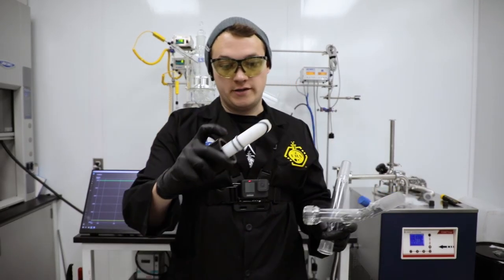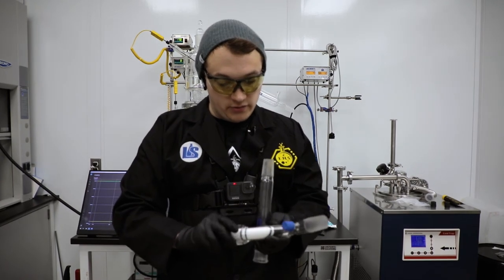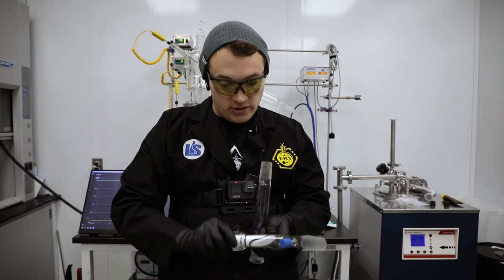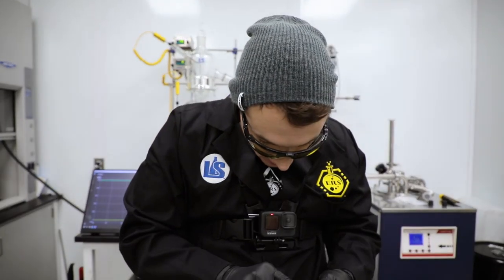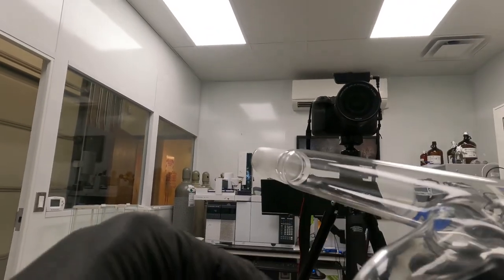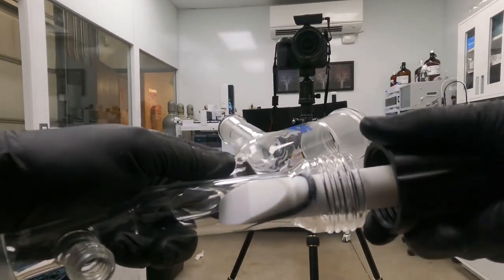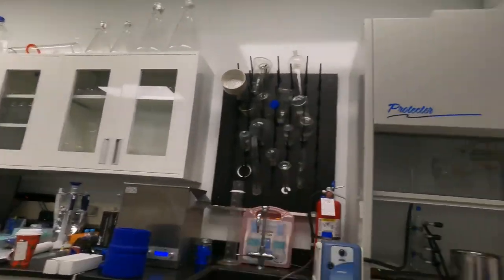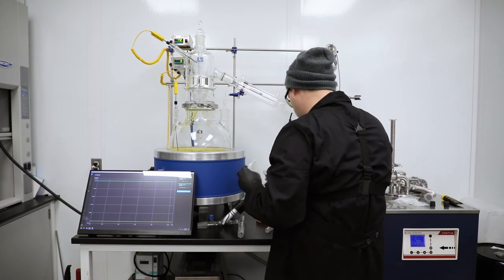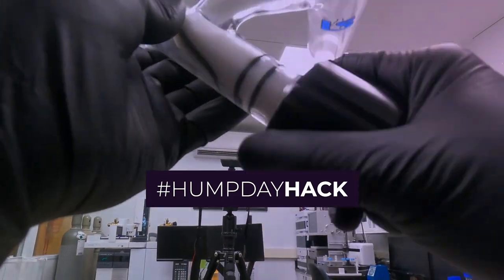With my upper o-rings greased and my lower o-ring serviced, I'm going to slowly insert this in, giving it a slight wiggle so that it's nice and seated, then start turning. One way you can tell if the o-ring is sealed is you can actually see it pressed against the glass. For the second one, as I insert, I want to give it some rotations. Okay, looks like we have a good seal on both. Two serviced pieces of glass — I've now serviced my valve swing arm and can assemble my system. We're good to go. Thanks for watching.